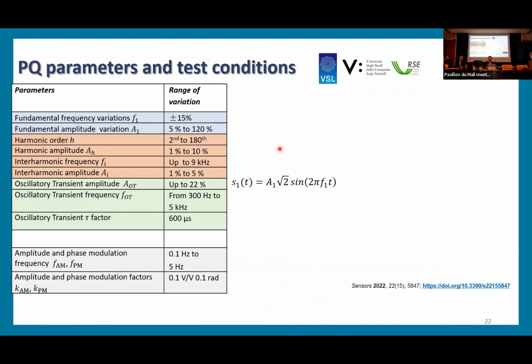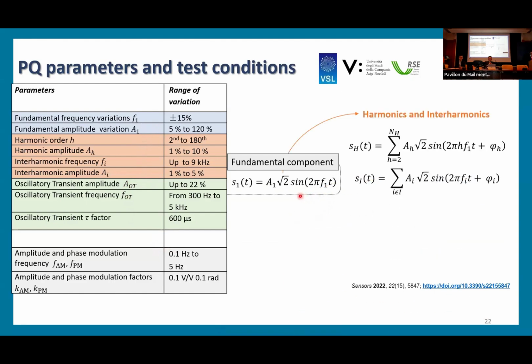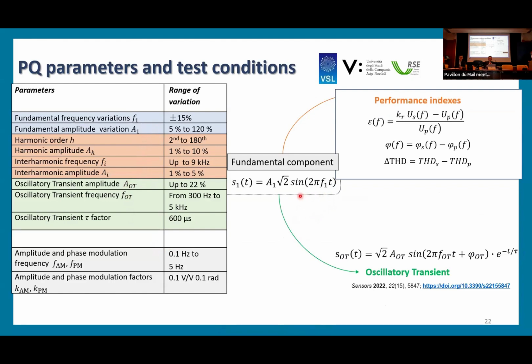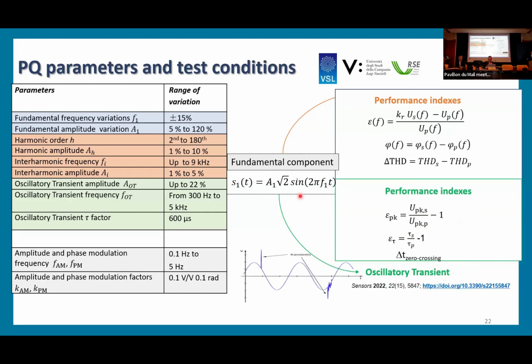So we started with the selection of the disturbances that were used for the characterization of IT performance verification. So stationary disturbances like frequency and amplitude variations, harmonics and interharmonics, but also oscillatory transient and, let me say, dynamic phenomena like amplitude and phase modulation. All these phenomena have to be superimposed to a rated voltage and frequency fundamental component. And moreover, performance indexes that quantified the performance of the instrument transformer in the measurement of a particular phenomenon were defined, both for stationary phenomena as well as transient phenomena.